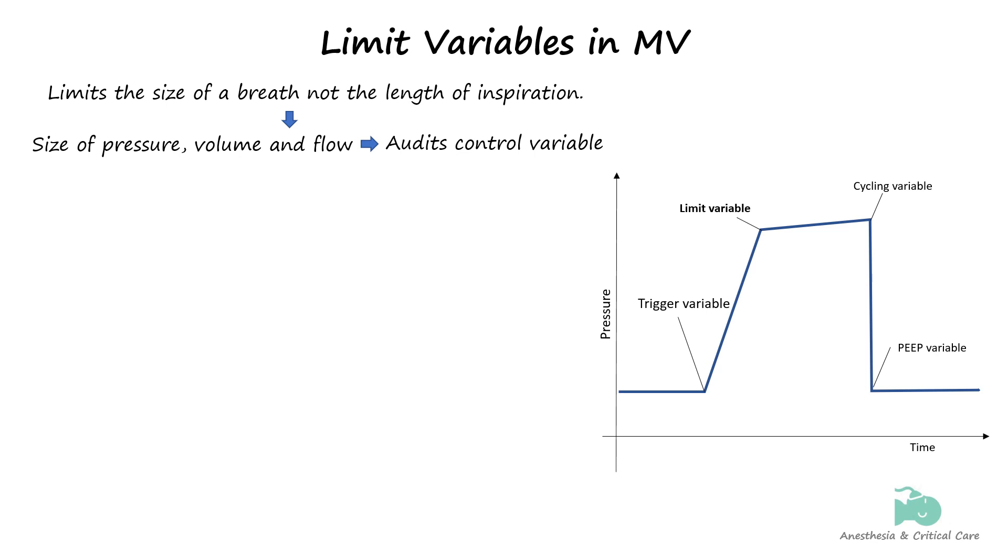When the volume limit is met, the inspiratory flow ceases. Unlike the control variable or the cycling variable, multiple simultaneous limits can apply to the inspiratory phase.